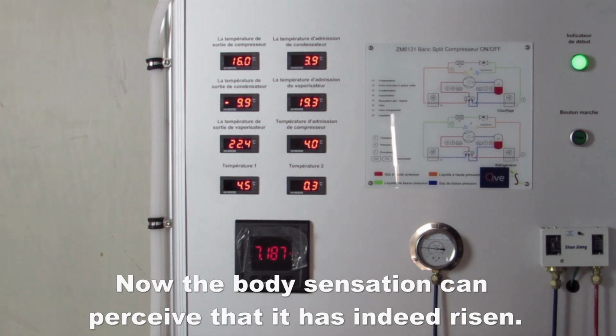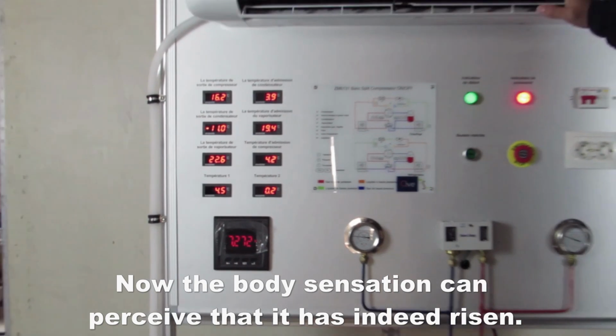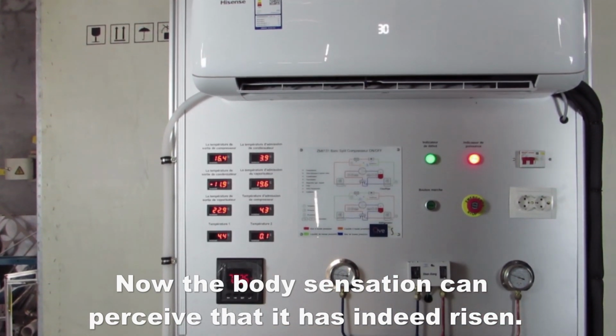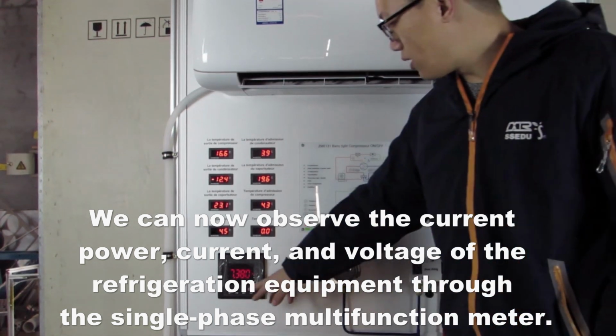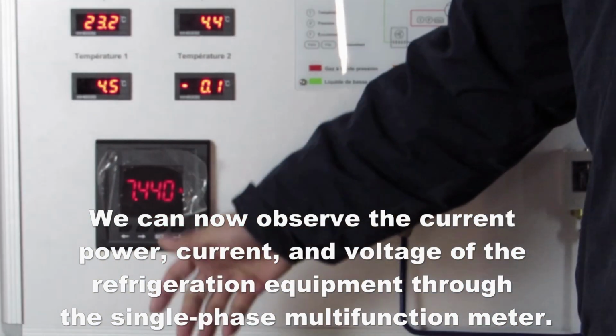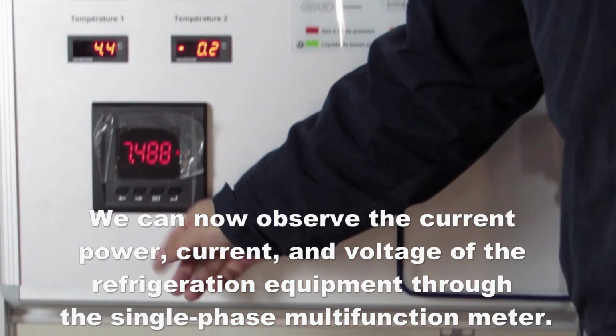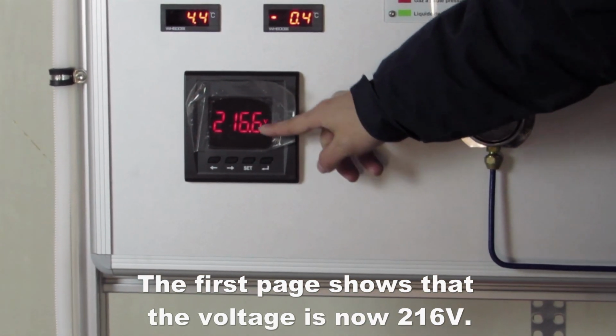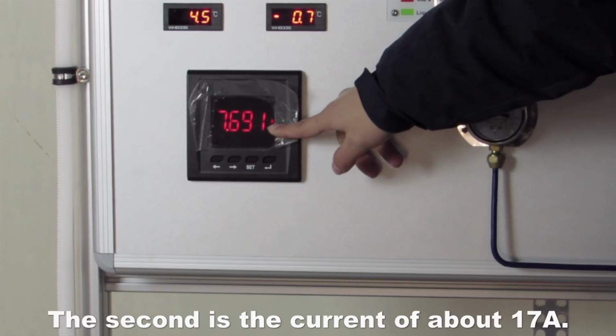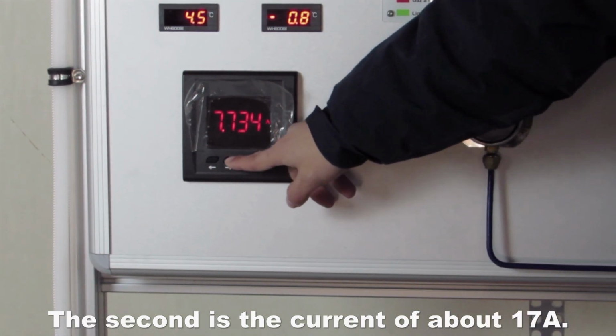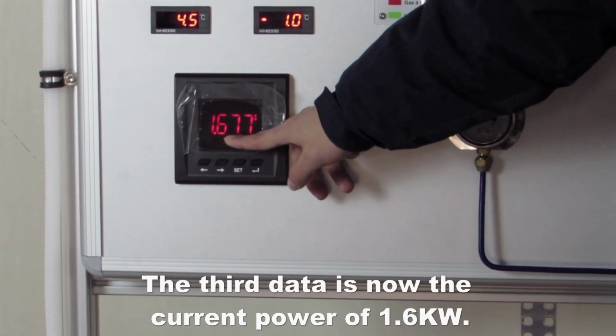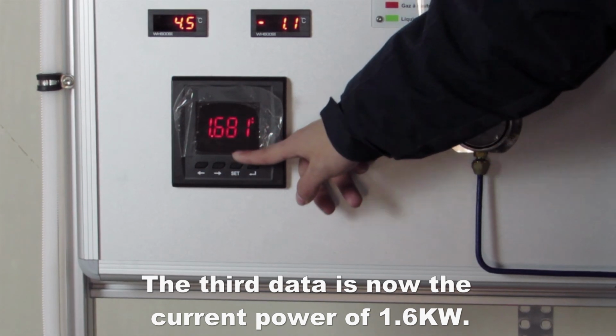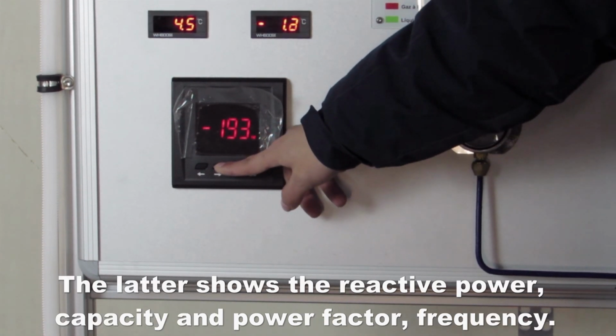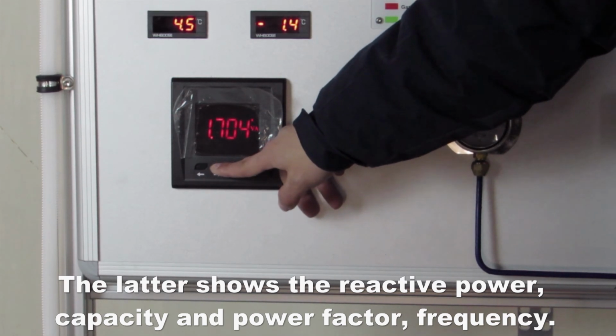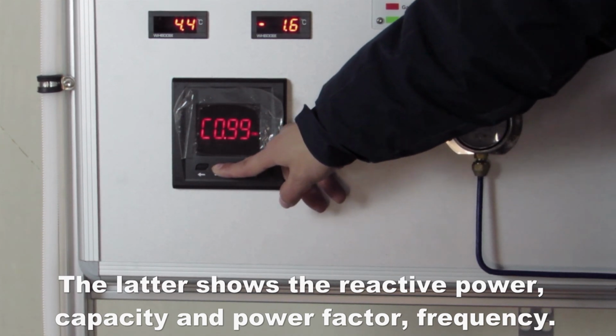Now the body sensation can perceive that it has indeed risen. We can now observe the current and the voltage of the refrigeration equipment through the single-phase multifunction meter. The first page shows that the voltage is now 216 volts. The second is the current of about 7 amps. The third data is now the current power of 1.6 kilowatts. The latter shows the reactive power, capacity, and power factor frequency.